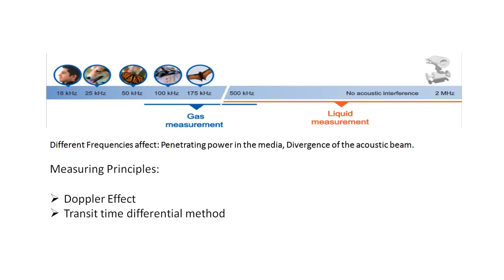Up to 20 kilohertz is known as the audio frequency range. Above 20 kilohertz is the ultrasound frequency range. Up to 500 kilohertz is generally used for gas measurement, and from 500 kilohertz to 2 megahertz it is used for liquid measurement. The different frequencies will affect the penetrating power in the medium and also the divergence of the acoustic beam.